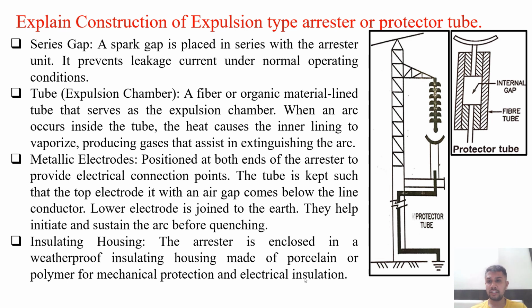Metallic electrodes. These metallic electrodes are connected on either side, positioned at both ends of the arrestor to provide electrical connection points. The tube is kept such that the top electrode, with an air gap, comes directly below the line conductor, whereas the lower electrode is joined to the earth. This is the top electrode and the lower electrode is connected with the earth. They help initiate and sustain the arc before it quenches.